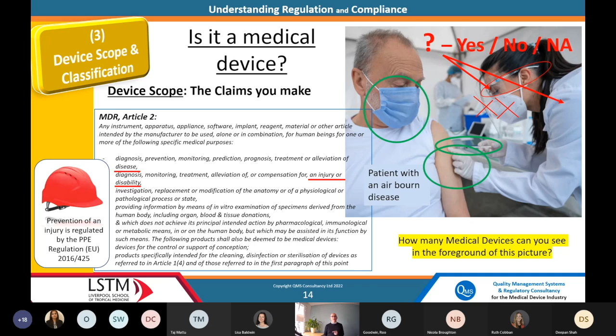Once you've determined that what you've got is probably a medical device, you've got to determine whether it's a medical device or an IVD. So I'm going to explain very clearly what an IVD is now. A medical device is something that touches the body or analyzes the body directly, and an IVD analyzes cells and fluids taken from the body, and the analysis happens away from the body. It could happen in a lab hundreds of miles away, or it could happen in a device right next to the patient, but it doesn't happen on the patient.